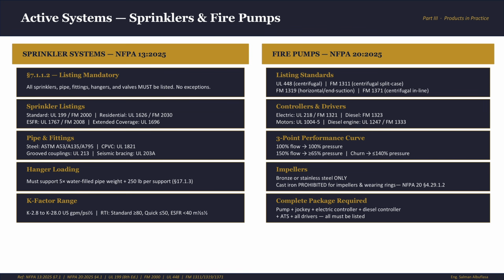Let's take an example of what that means. Let's say I have a low risk storage area. Everything is compliant. My sprinkler system is designed, calculated, and listed for the type of hazard. I have my safety certificate from the civil defense. Then I decide to change my business, to change the products. I will have a high risk storage area, more materials, different types of materials, different fuel loads, more combustible materials stacked together and higher than before. What changed? The hazard classification has changed entirely. But I haven't bothered to inform the civil defense or the local authority.